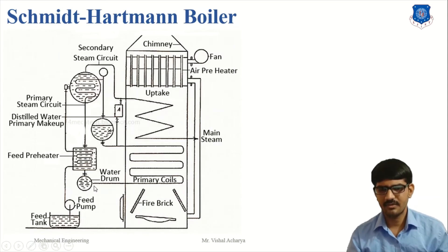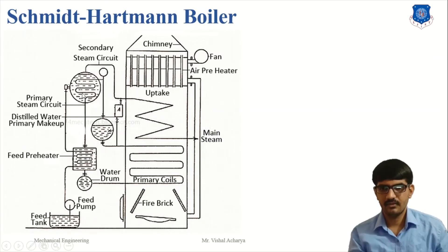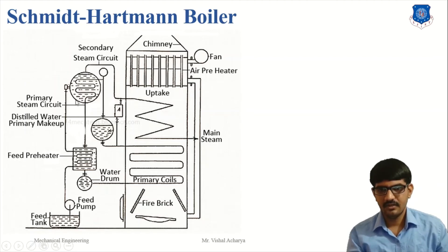Water is transferred from the water drum to the primary coil, i.e., the primary evaporator, where water is converted to higher pressure, approximately 100 bar, and transferred back to the water drum. Then steam is supplied to the secondary drum. In the secondary drum, it passes through tubes where higher pressurized steam supplies heat to the lower pressurized steam, meaning the impure water. The impure water is then converted into steam and passed to the superheater.